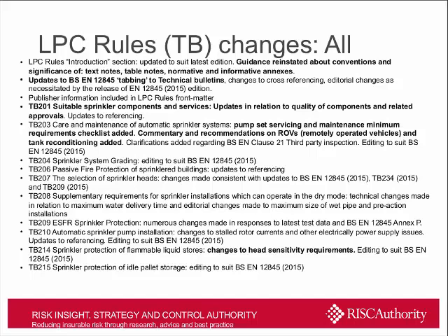In TB 201, which deals with suitable sprinkler components and services, we've added a few new line items to the table in that technical bulletin. That's to bring check valves and non-return valves into approval schemes. This year we've stopped short of specifying which standard they should be approved to, but they are in the table. That's to flag the intention, and we would like to bring them properly within all the schemes. They're critical system components after all.